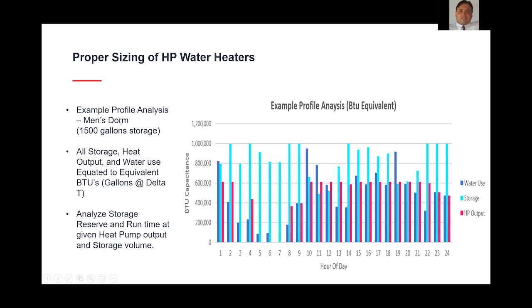This is an example from an actual men's dormitory. I think this was like 450 people with 1,500 gallons. And I think this was an example where it was extrapolated to a max hourly condition per ASHRAE. And so you can see what this profile looked like when this was mapped out over the course of 24 hours. So in this scenario, we were pairing, I think, over where you can see here in the graphs, over 600,000 BTUs, 600 MBH worth of CO2 heat pump water heaters, along with 1,500 gallons of storage.